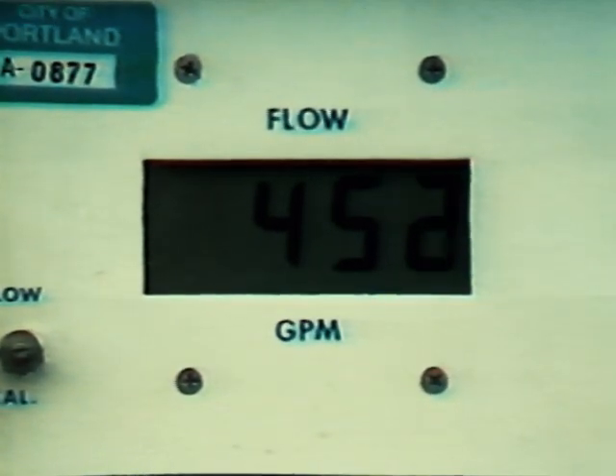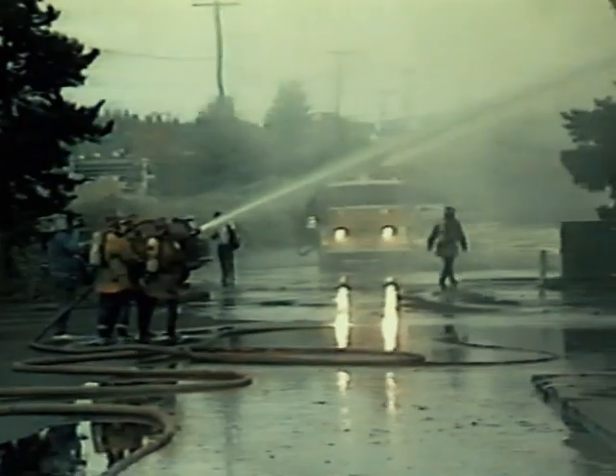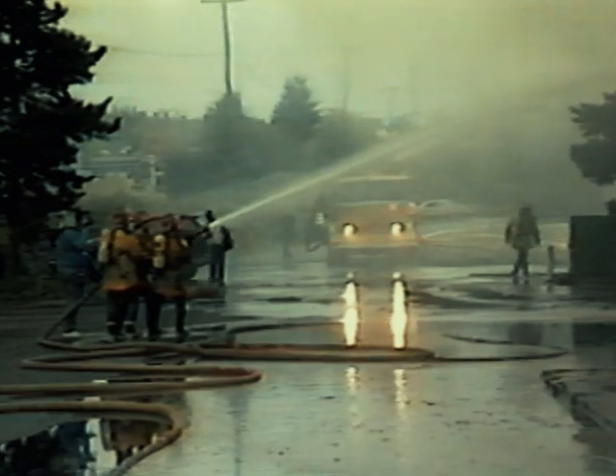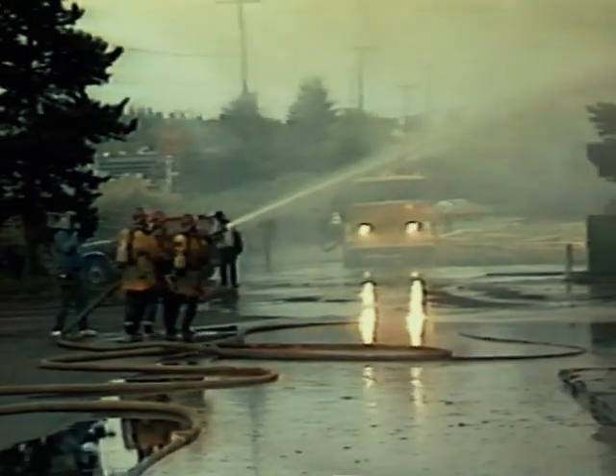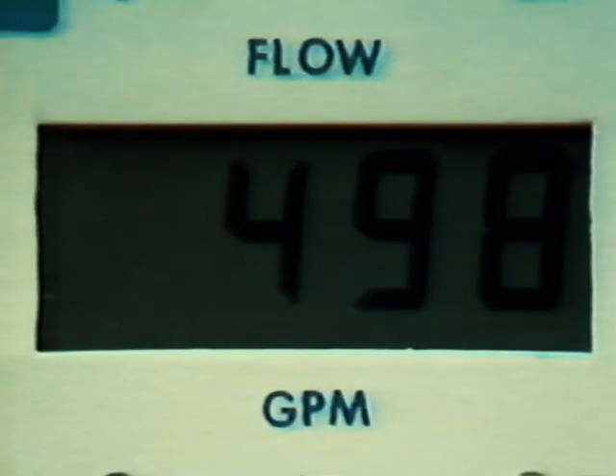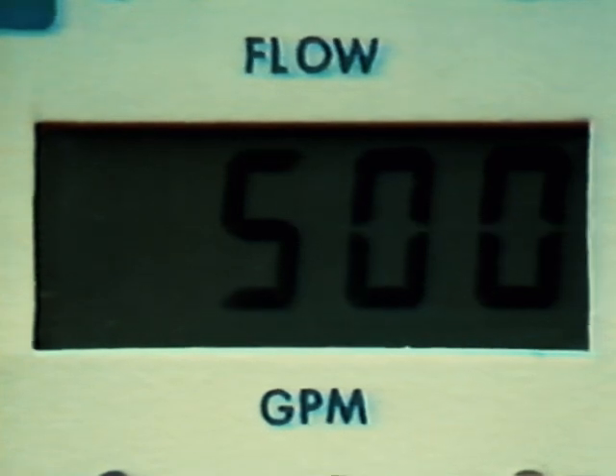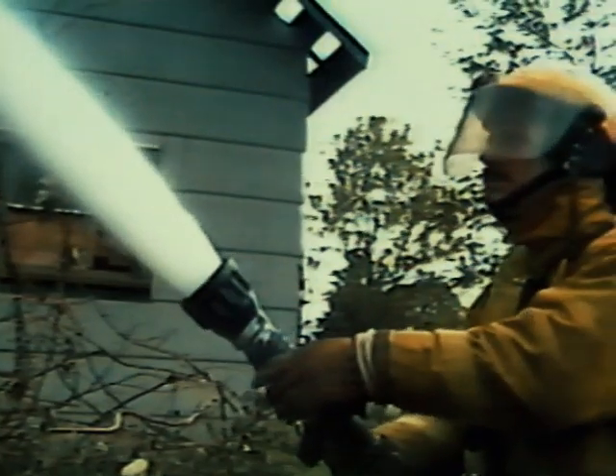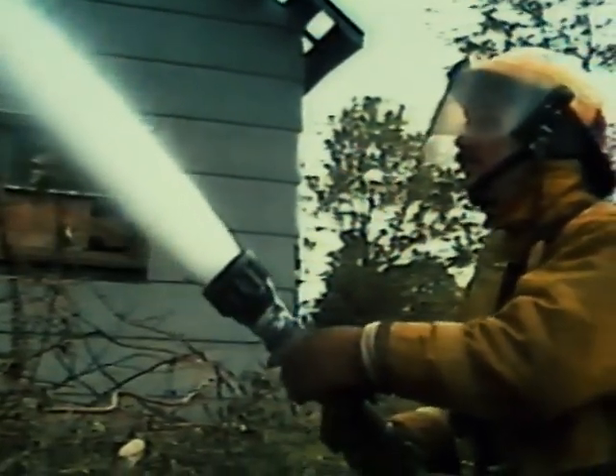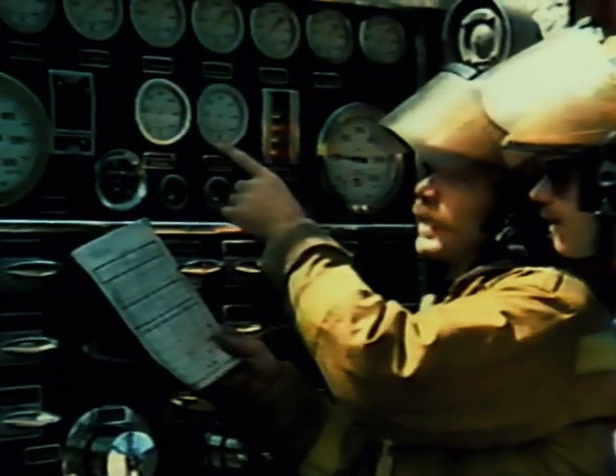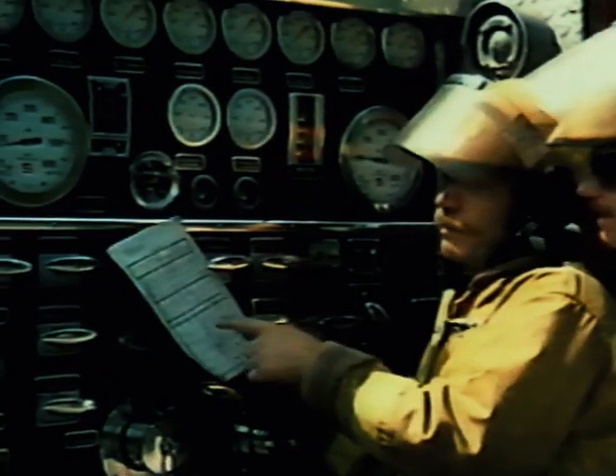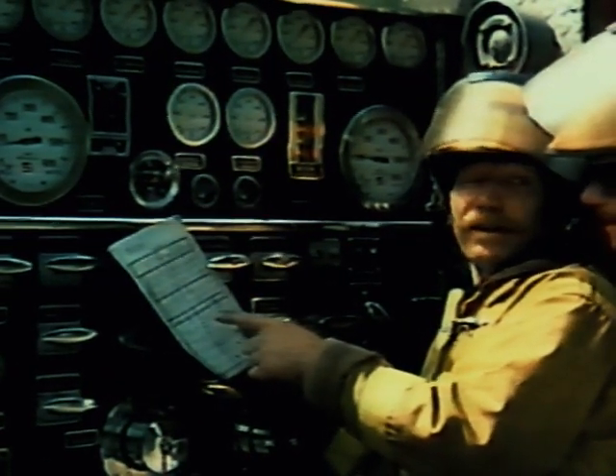square inch. Flow meters can simplify your duties at the fireground by reducing the number of manual hydraulic calculations needed to produce an effective fire stream. With a flow meter, the flow of water from the pump discharge is the same as the flow of water out of the nozzle. Manual calculations for friction loss or hose layout are not necessary.